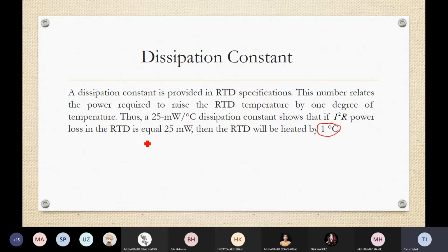Okay? So let's say we have to measure a temperature of 100 degrees Celsius, and there is some power loss because of the external power supply in the RTD, and that power loss is 25 milliwatts. So therefore it is going to heat up the RTD by 1 degree. So therefore the reading will be modified to 101. So therefore there is a chance of error because of this power dissipation.